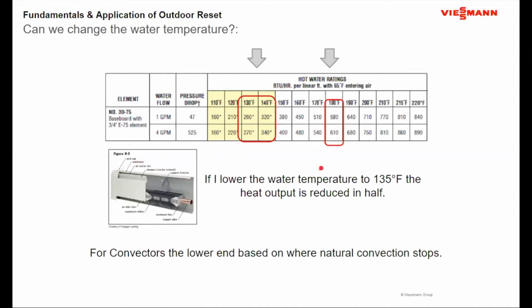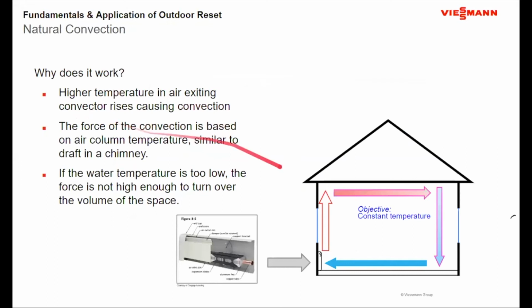Okay. Now, one of the things that does come into play, and you'll notice when you start to look at convectors, for instance, baseboard, fin tube baseboard is considered a convector. Most manufacturers stop at some point. Here it happens to be 110 degrees. And why you tend to see that drop off at the end here is really this. The water temperature passing through that baseboard has to generate the force to force natural convection movement of the air within the room. And the problem is if the temperature gets down low enough, you may not generate this convective current.